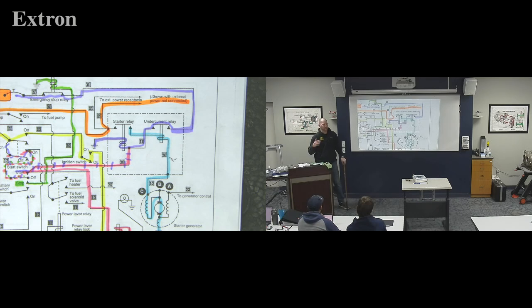Once they're spun up, the amp draw would lower on them. So step one would be grab one of our gyros and see what the amp draw does and if it stabilizes. Step two would be, could we get a relay that would be closed when it's spinning but opens when it spins up?